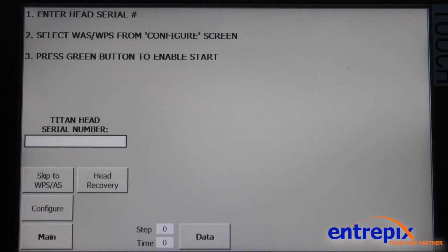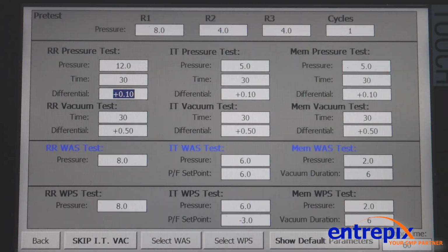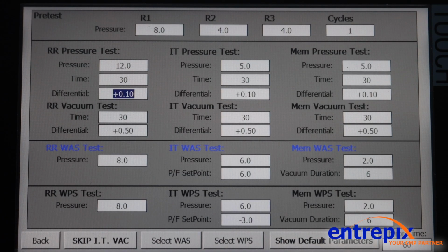Once you've selected your configuration, you'll want to set up your testing parameters. This is accomplished by selecting Configure. The parameter screen is divided into several sections, allowing you to customize the zone pressure set points, the allowable leak pressure delta, and the leak check duration. You can also customize the number of pre-test head pressure cycles, the zone pressure values, and customize the wafer present or wafer absent sensor verification test.